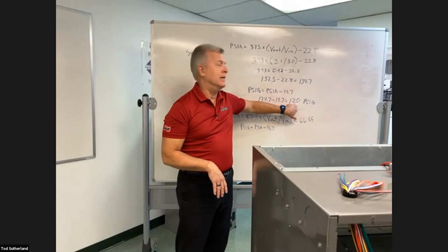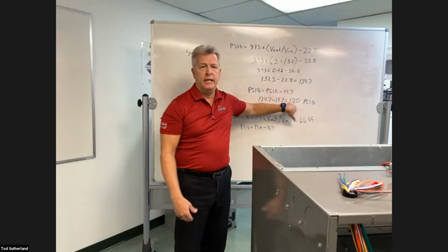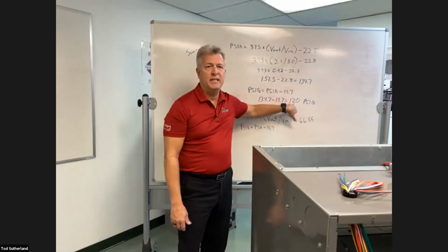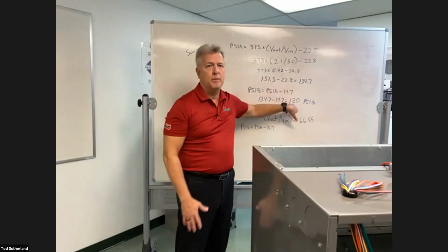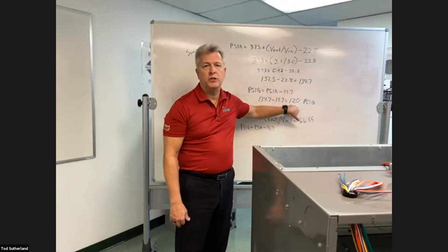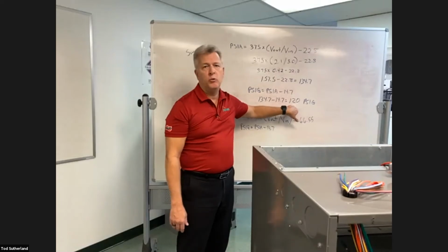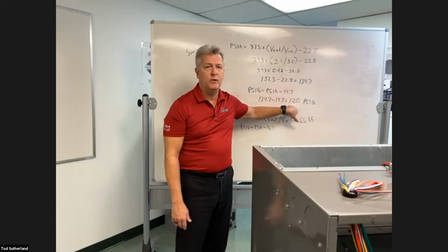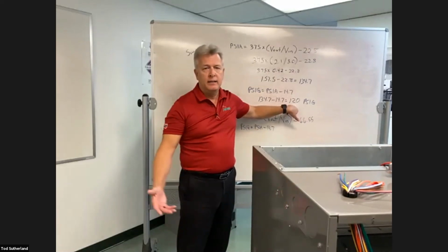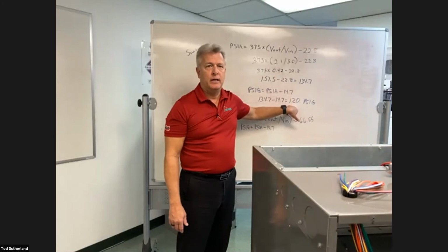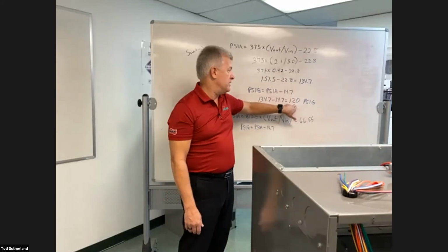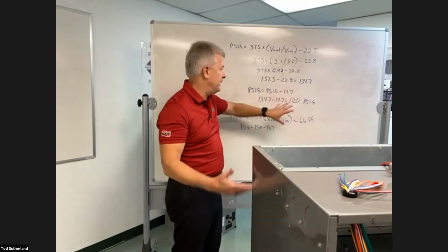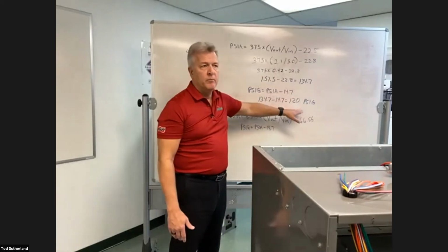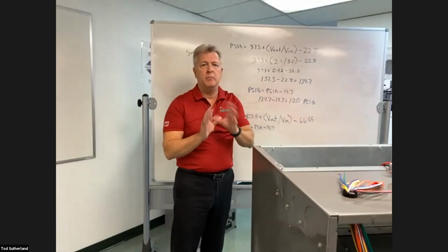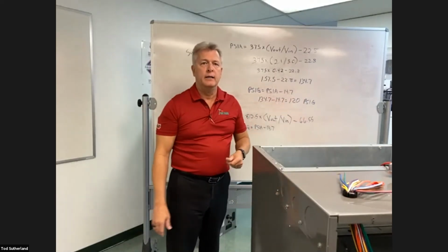If you're reading 120 here and your manifold set is reading 57, then there's a problem. If you're reading 57 here, but your manifold's reading 120, then you've got a problem. If you're reading 120 here, your manifold's reading 118 or 123 or 125, then you don't have an issue. So this is meant to give you an exact reading. Well, it is, that's what the valve's reading, but just realize you just need it to be close to what your manifold's reading, okay?